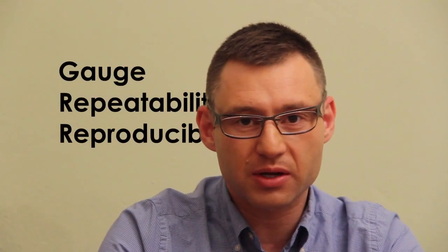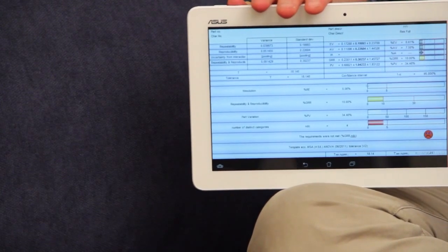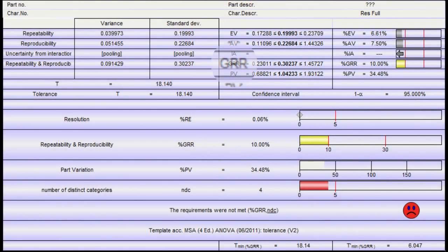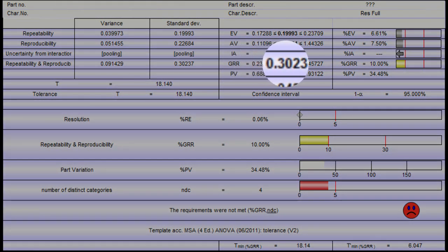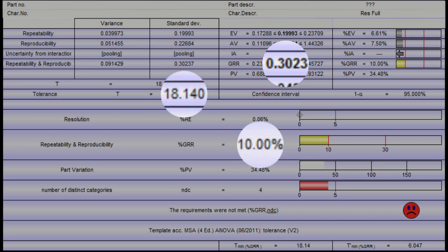Let's see for example the gauge R&R. Here is data presented in the MSA, the measurement system analysis manual. The total gauge R&R is a little over 0.3 which makes the measuring device acceptable at 10% gauge R&R for a tolerance of 18.14.